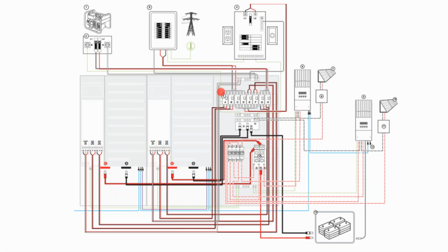What you would do in that circumstance is not use the automatic generator controls that come with the battery inverter, and instead put the generator on an interlock switch that either locks out the inverter breaker or locks out the generator breaker, and just do it on an automatic transfer or a manual transfer. Manual transfer switches are pretty cheap.